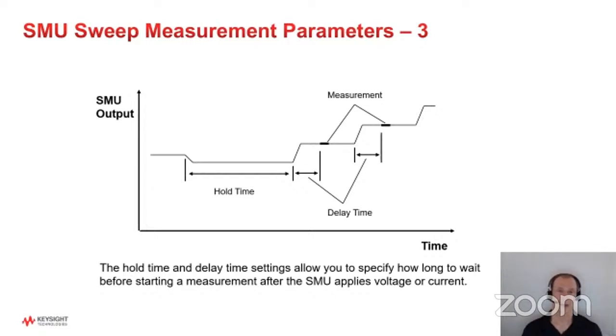It's very important to understand the timing parameters for a sweep measurement, because in the end that can determine how good your data is. You can set both a hold time and a delay time. The hold time is the initial time before the sweep actually starts. The delay time is the time the instrument waits after you change to the next value in the sweep before it actually starts making the measurement. Why do I want to do that? If I have a lot of capacitance or other factors affecting my measurement, it allows the values, voltages, and currents to stabilize before I try to make the measurement.